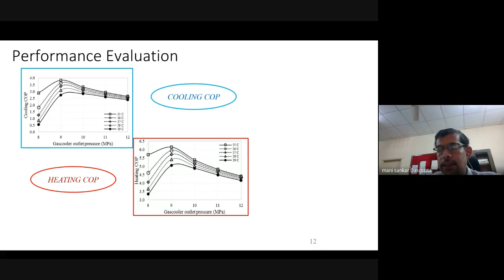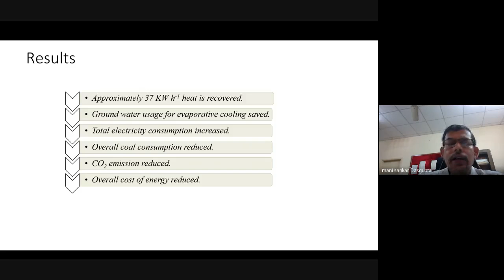Overall, approximately 37 kilowatt-hours of heat is recovered, which was otherwise rejected to the atmosphere. We also reduced groundwater use for cooling. Total electricity consumption increased because we had to run an additional compressor, but overall coal consumption is reduced drastically, CO2 emission is reduced, and overall energy cost is also reduced. We did some preliminary cost analysis and found the additional cost can be recovered in about 18 months of operation.